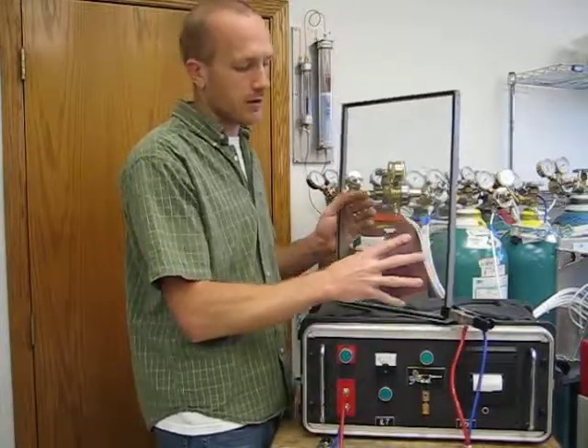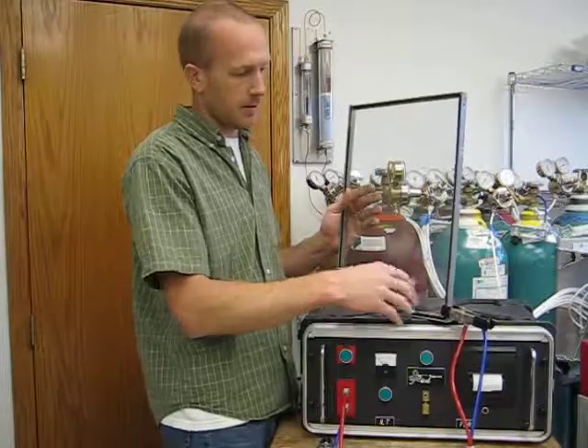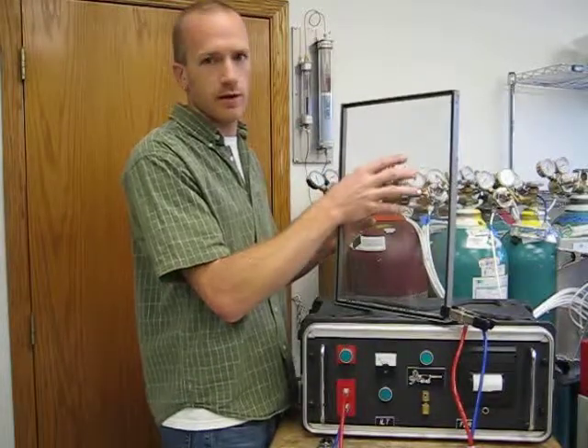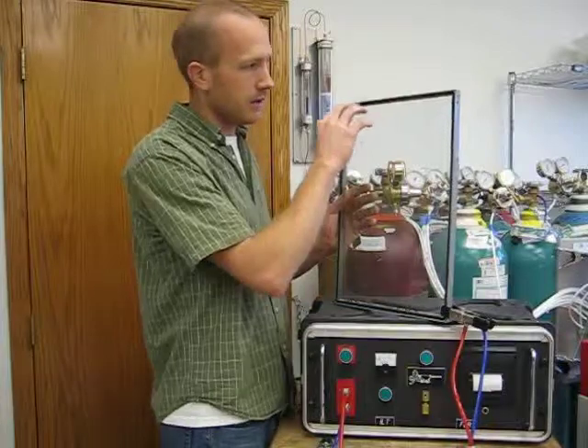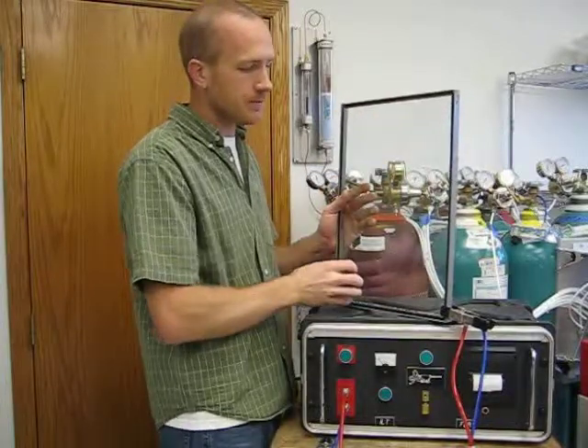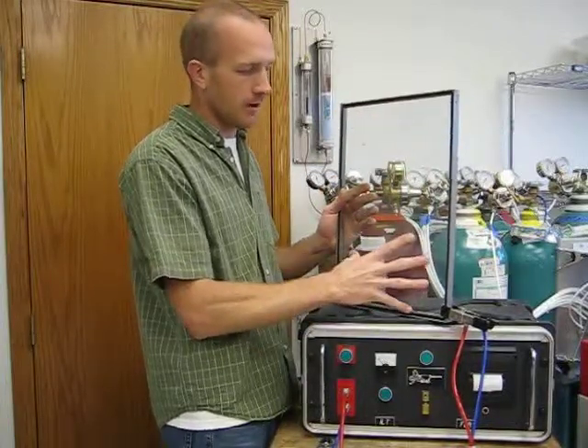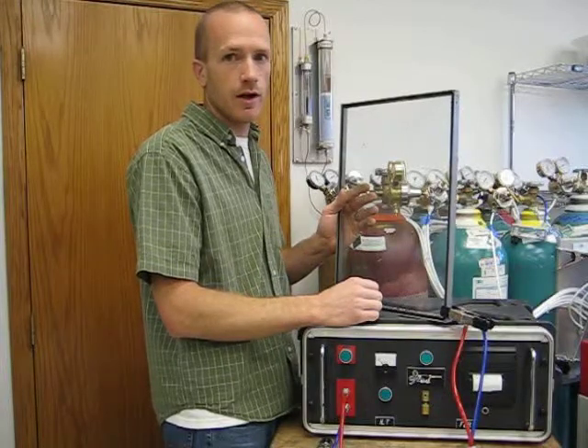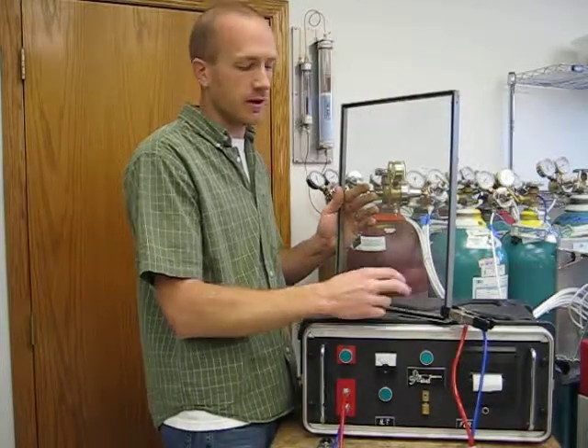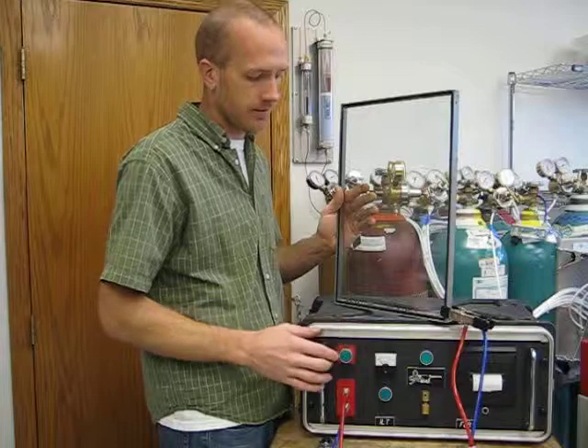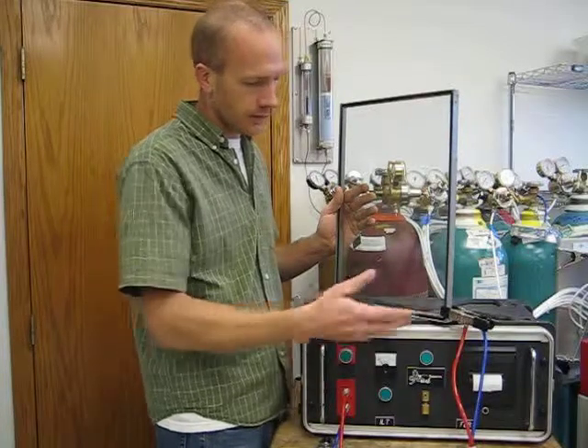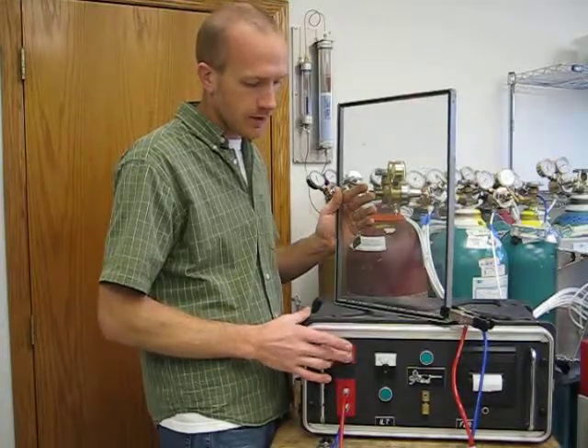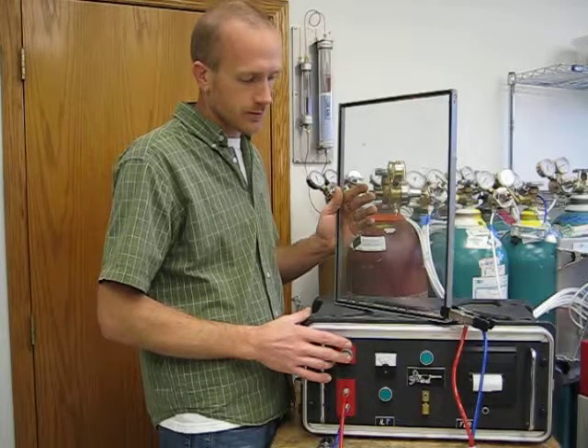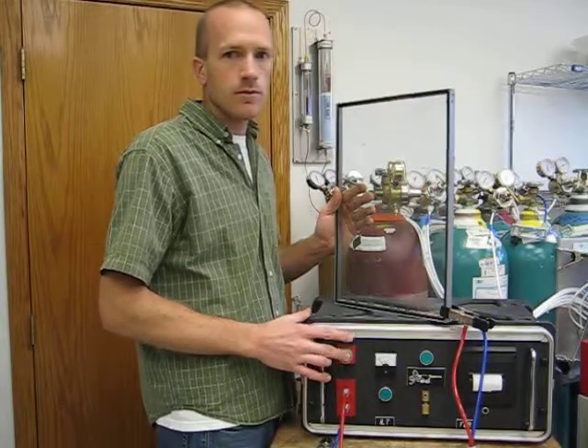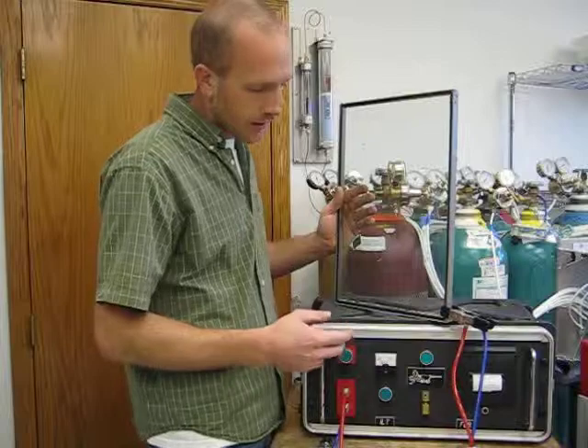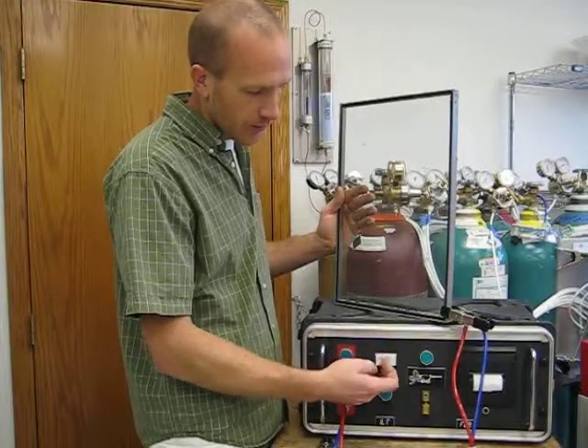This is a real good method for testing because it homogenizes all the gas that's in there. There won't be any corners or larger areas that have a higher or lower gas concentration as it effectively mixes it. Once the lance is put in, the machine is started. You can hear the pump starting, and the meter will start moving on the front.